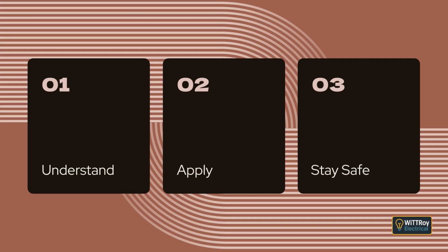Subclause C explains that the neutral and earth conductors must not operate in parallel. An exception explains that when connected to a distribution switchboard and operating on the alternative supply, the submain neutral and protective earthing conductors may operate in parallel through a remote MEN connection if the conductors are not overloaded by current sharing, the conductors are suitable for the maximum fault current, the copper earthing conductors meet the requirements of Clause 5.3.3, and the current carrying capacity of the neutral conductors is not less than their associated active conductor.